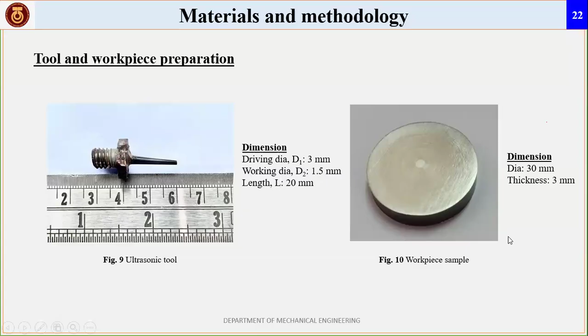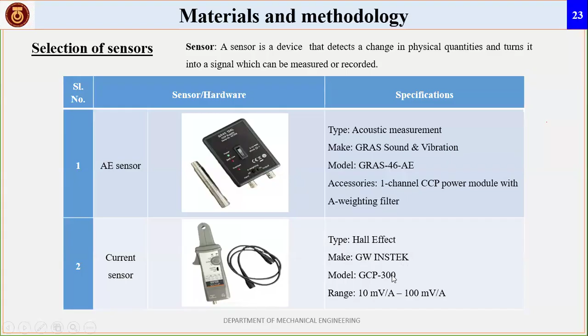The selection of sensors. The AE sensor with this specification: its type is acoustic measurement. It's made by GRAS Sound and Vibration. The model is GRAS 46 AE. Its accessories: one channel CCP module with A-weighting filter. The current sensor is a Hall effect current sensor made by GW Instek. Its model is GCP 300. Its range is 10 millivolt per ampere to 100 millivolt per ampere.